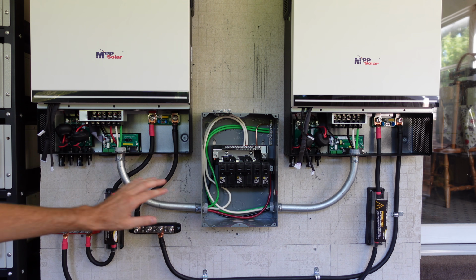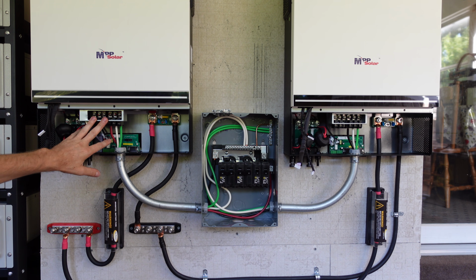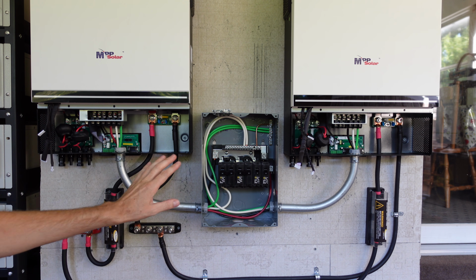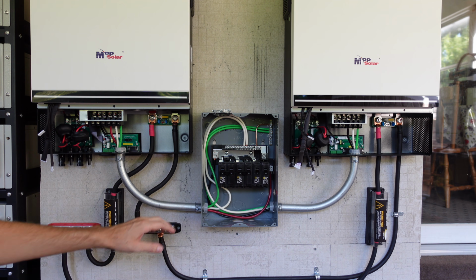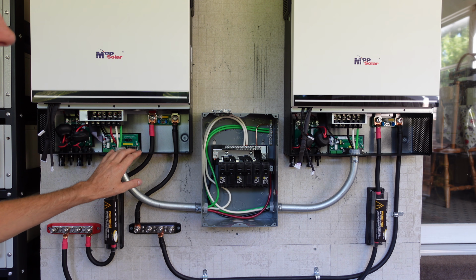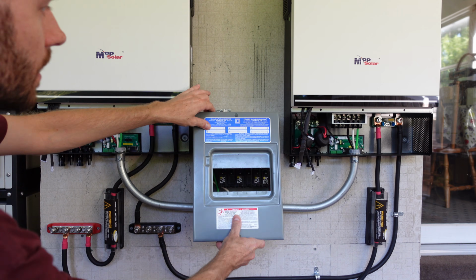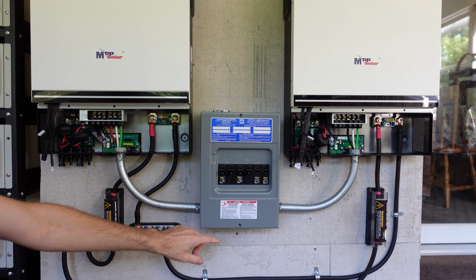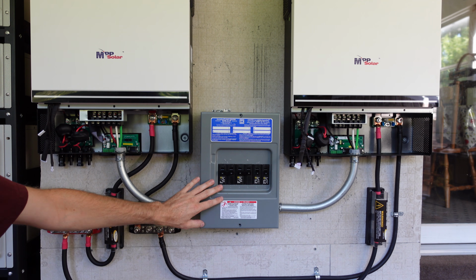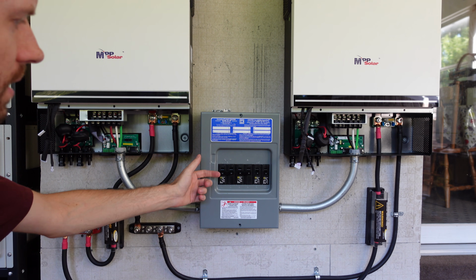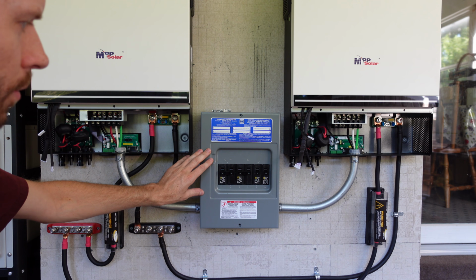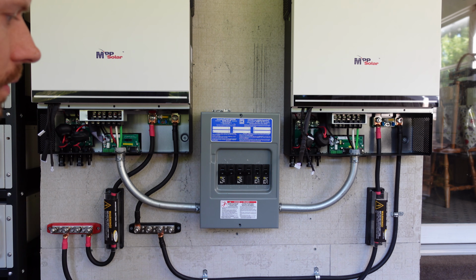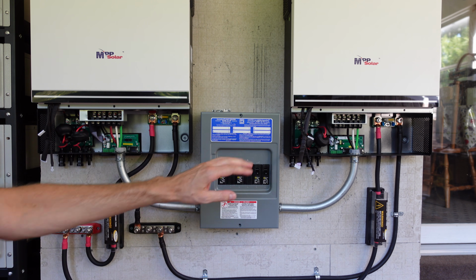I've now double and triple checked all of the wiring, both the AC and the DC side of both of these inverters, the circuit breaker panel. I've checked the torque of all the bolts, so I'm ready to put my breaker panel on. You see, I've put a few breakers in here. I don't plan on using all of these breakers. However, since I've already punched out the knockouts in the cover plate, I want to make sure they're covered for safety purposes. And I'm also ready to put the front panels back on both of the inverters.